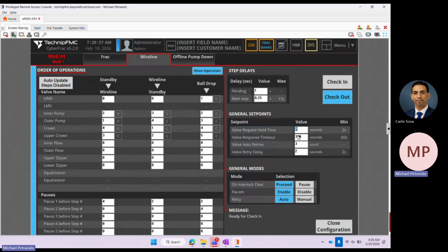The rest of these we don't really mess with, so I don't think we have to get into them, but some are self-explanatory, like auto retries. If the valve fails to respond, the sequencer will send another request up to 3 times. I can tell it to never send another request, in which case it would be 0. If it tries however many auto retries you have set and still fails, it'll say the valve failed to move and it'll just lock up, and you need to go fix your valve.